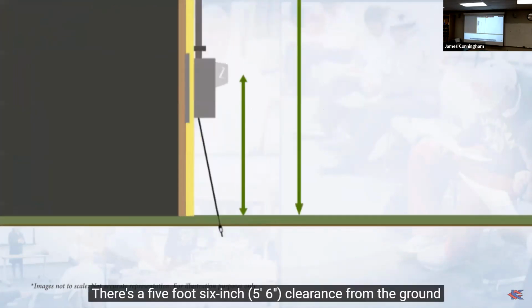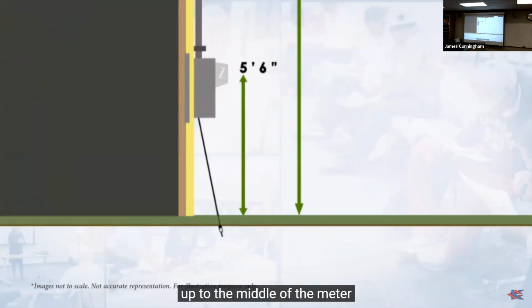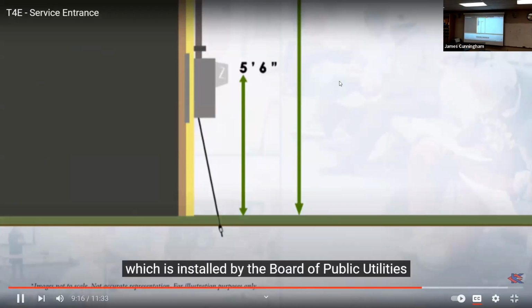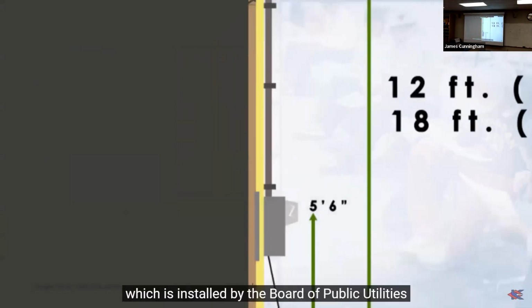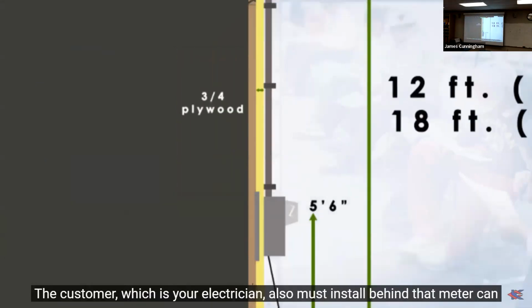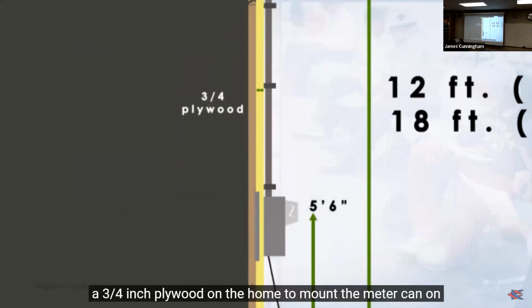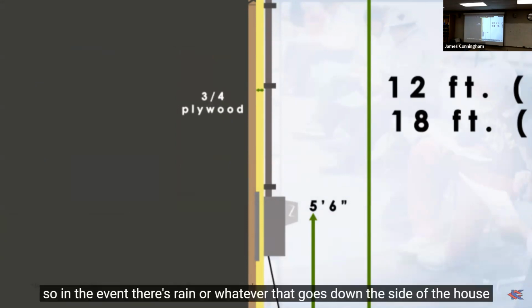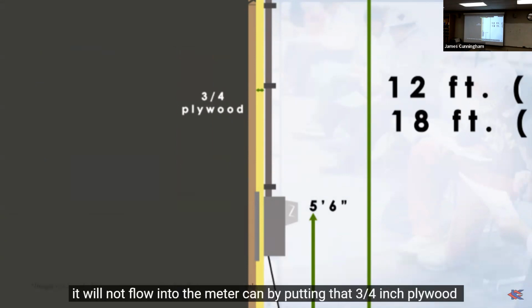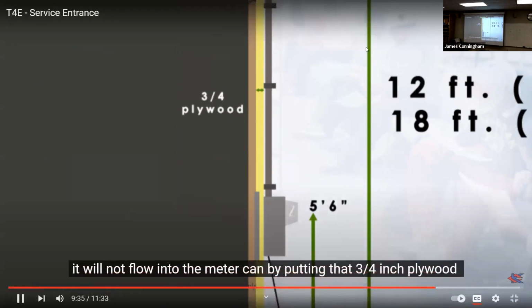There's a 5-foot 6-inch clearance from the ground up to the middle of the meter, which is installed by the Board of Public Utilities. The customer, which is your electrician, must also install 3/4 inch plywood behind that meter can on the home to mount the meter can on. So in the event there's rain or whatever that goes down the side of the house, it will not flow into the meter can.